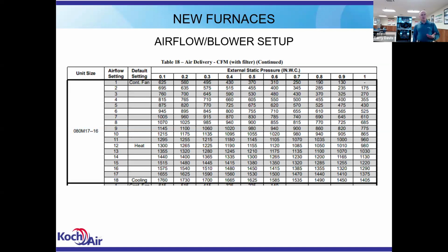Now in cooling mode, that fan speed is always going to be at the highest setting, because when they build the furnace, they have no idea what size air conditioner you're going to put on it. So they just program the board to be set at the highest fan speed. That way they know they got enough air going. Now that thing may sound like a jet engine if you have a 4-ton drive, if you only have 3 tons of duct, you're going to have to go in and set that, but it'll run.